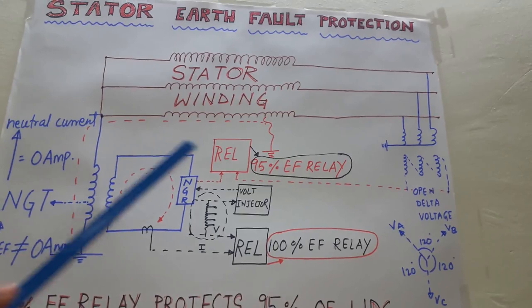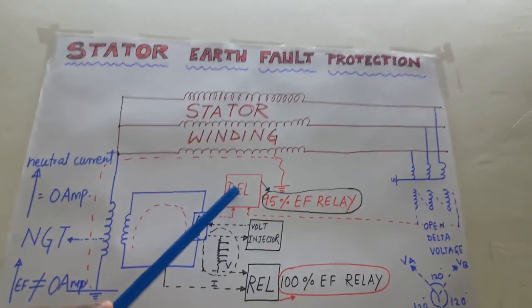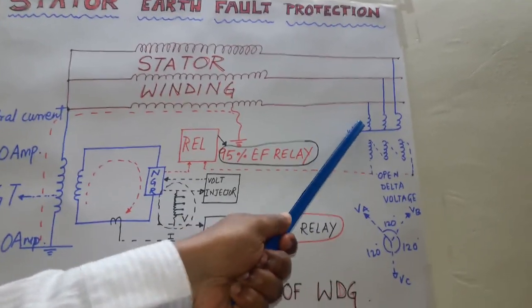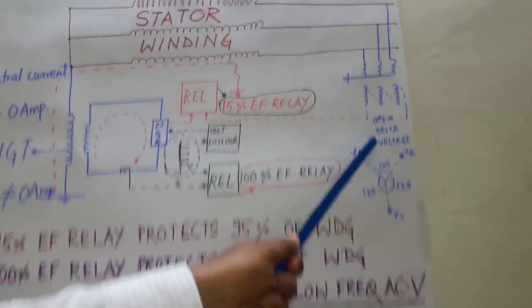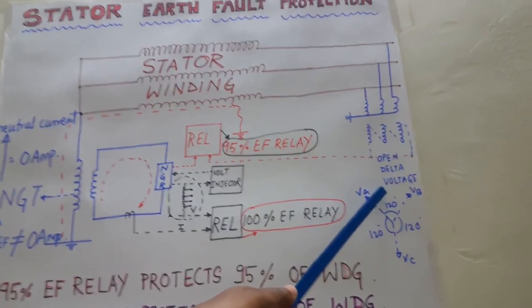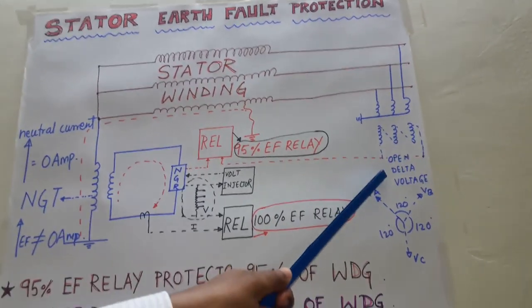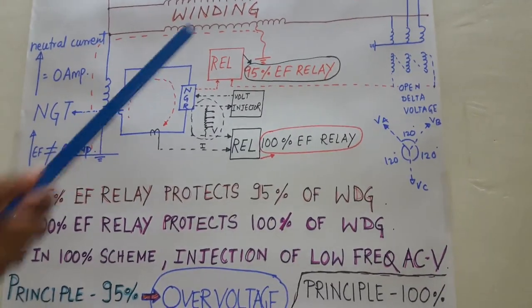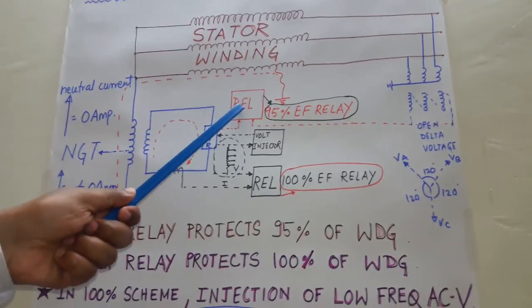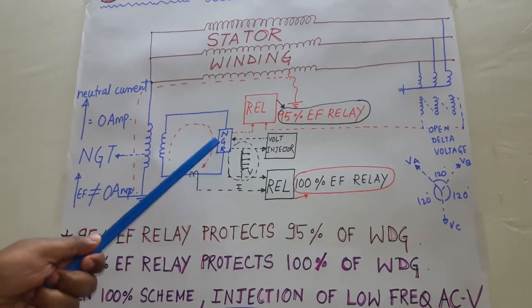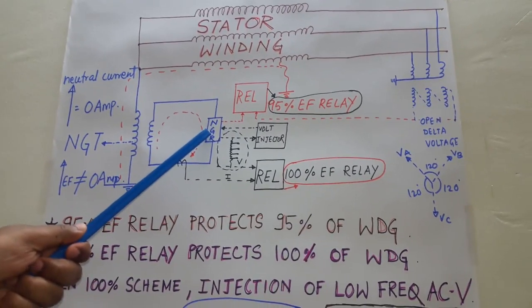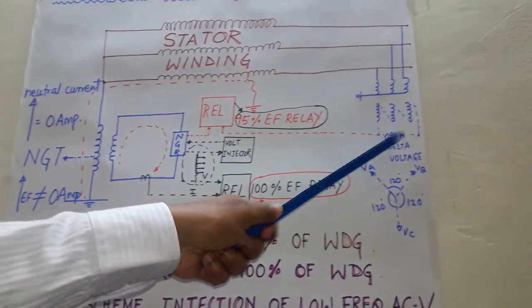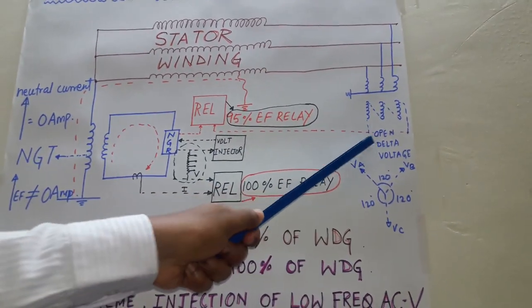The relay can also take one more input from the generator PT — the open delta voltage input. It can act as an extra condition for the relay. If you are setting the NGR level at a very low value, we can take one extra condition as the open delta voltage.